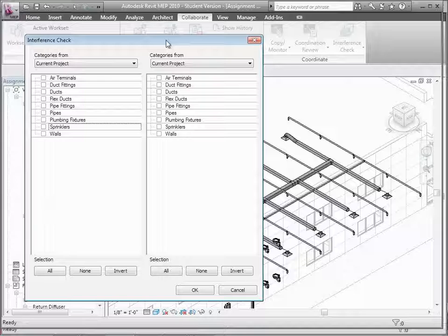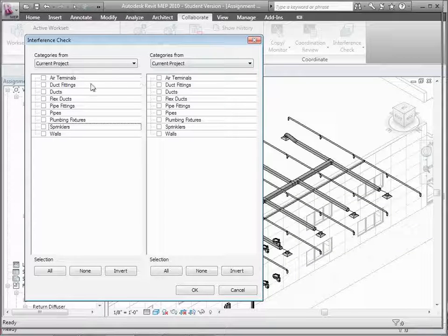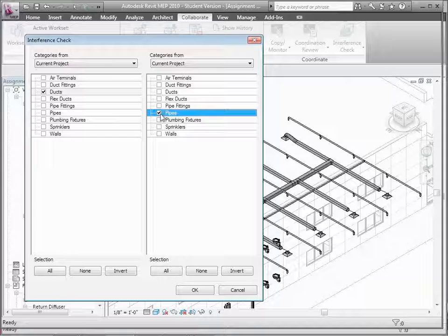It's much smarter to look at specific items and focus on types of interferences you're looking for rather than just saying intersect this whole model with that whole model. If you just say intersect a whole model with another one, there could be thousands of results, and you'll spend all your time sorting out the good from the bad. Let me look at the ductwork on one side and the pipes on the other side to check for duct-pipe interferences.